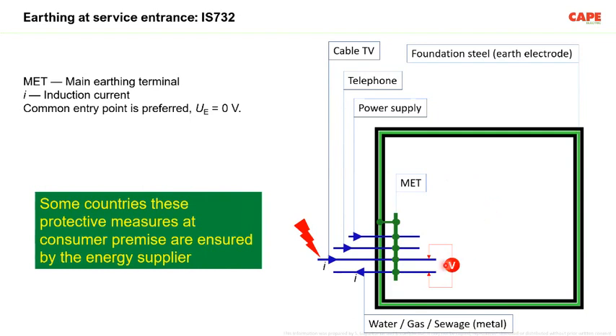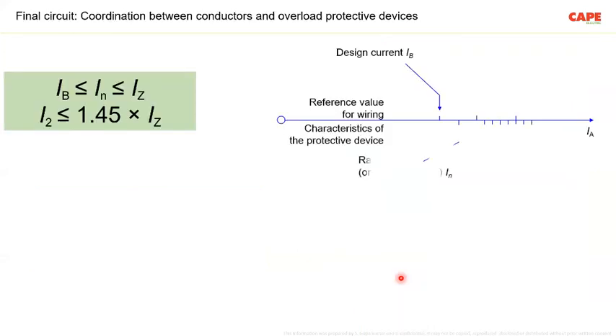So it's very important. In some countries, this kind of protective equipotential bonding is ensured by the energy supplier. While checking, they also ensure that the equipotential bonding is made properly. Whereas in our case, regulation 33 says you should check the insulation resistance every 5 years, but that basic itself is missing.